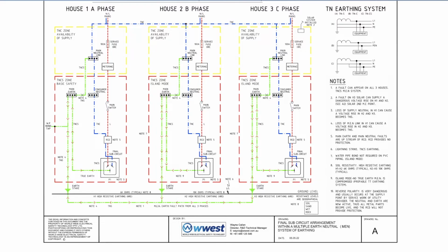Note 7 is your water pipe bonding, not required on PVC piping, which is your island mode, and that's what these ones here are. There's your note 7. There's no external taps that are earthed. There's no point, because they're all isolated, and that's why we use this term up here, island modes. So we go down and we have a look at note 8.